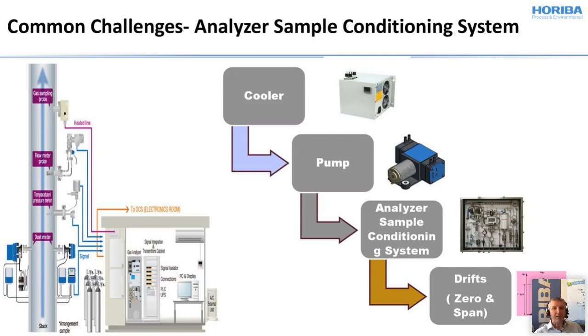Next topic, the pumps, which are used continuously 365 days in a year. The pump selection should be very accurate and should be designed to give the designated flow rate to the analyzer only. The analyzer sample handling system should be designed in such a way that there is negligible change in the representation of the sampling. This is what I mentioned before: the analyzer can be the best in the world, but if the sample handling system changes the gas concentrations, the analyzer can't analyze in a good way.